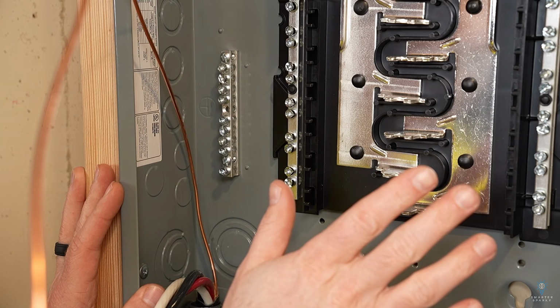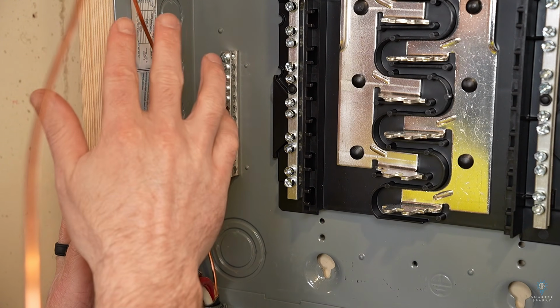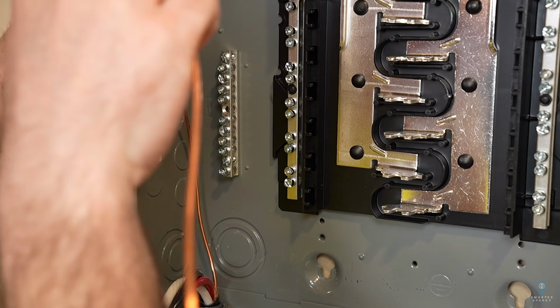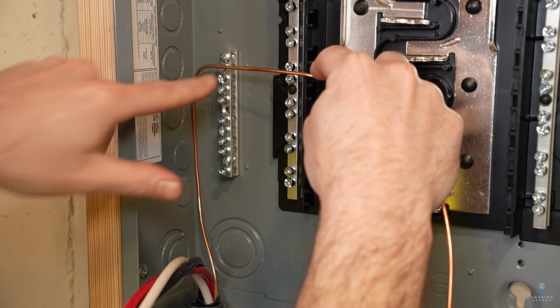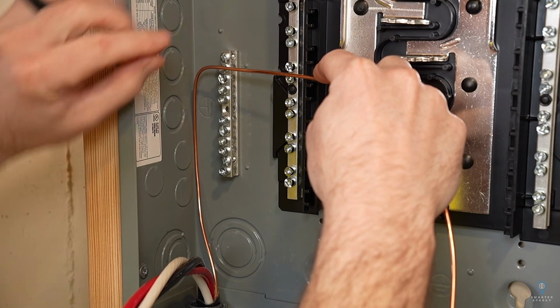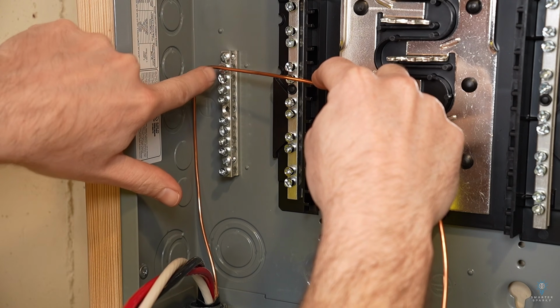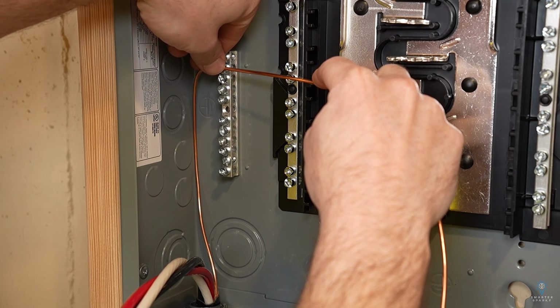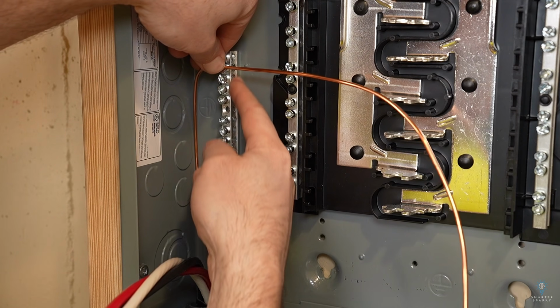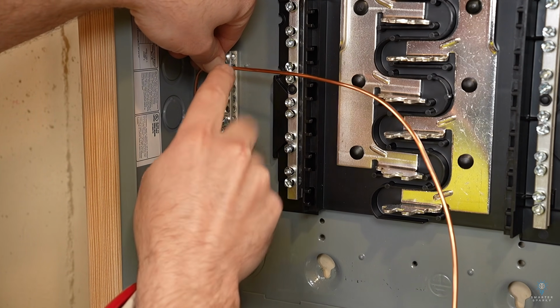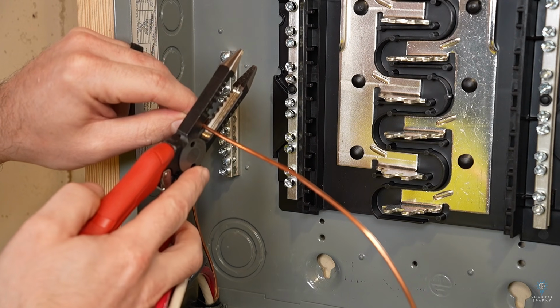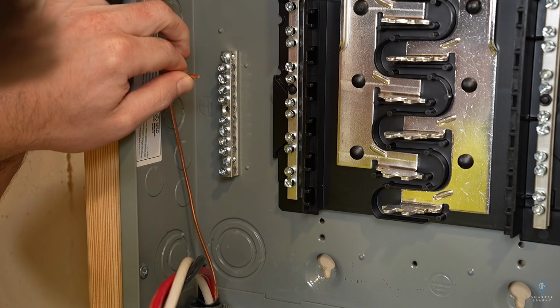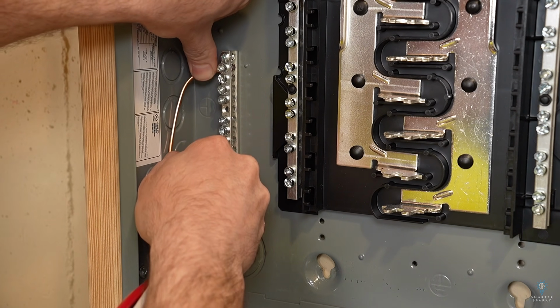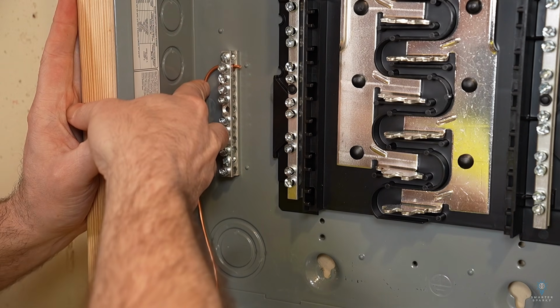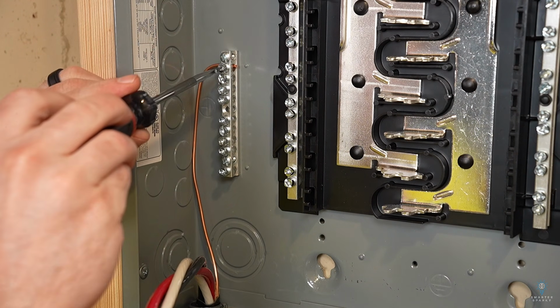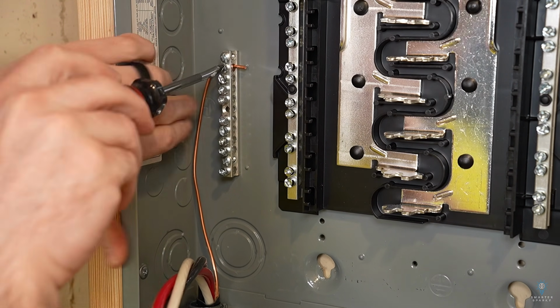So because that lug and that other ground bar is too big for this 10-gauge ground wire, I'm just going to install it in this top hole in this left side ground bar. I've got it aiming right for that hole, so I'm just going to hold my thumb on the other side of the bar here to give me where I need to cut, and make a cut right there. And then we can pop it under that screw, fold it into place so it looks nice, and then we can go ahead and tighten that screw down.